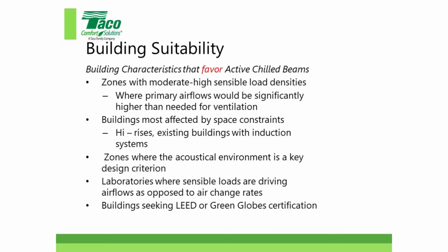So here are some buildings that favor a chilled beam. And I'm going to show you some pictures of chilled beams in case someone has never seen one, or some radiant piping. That's what this is. Instead of radiant heating, maybe in the floor or snow melting that some of you may have heard of, this is for radiant cooling, okay? One of the key items is moderate to high sensible load densities, okay? So that's something to consider. Some zones with moderate to high densities. Also, high rises, existing buildings with induction systems. That's a potential that we've seen in the marketplace.